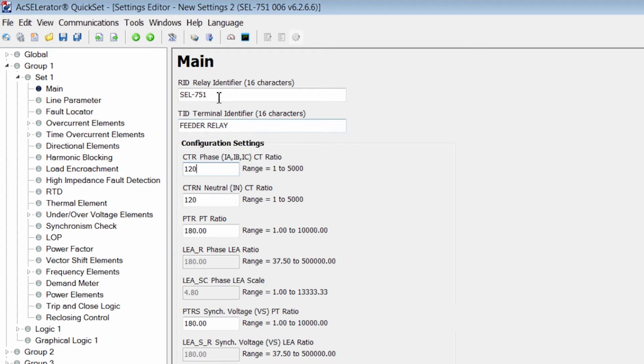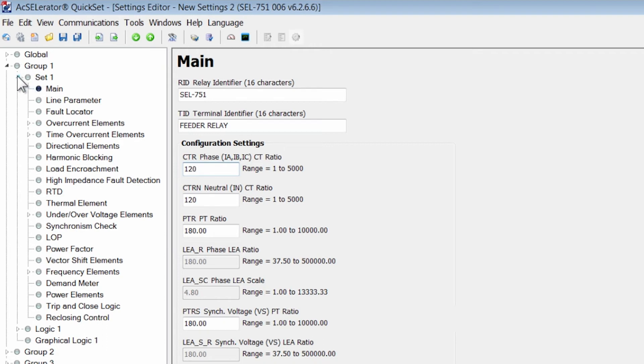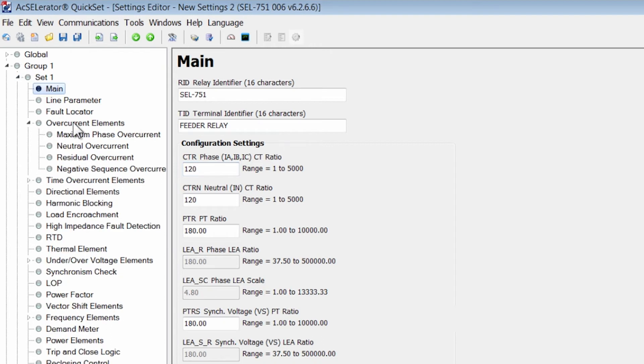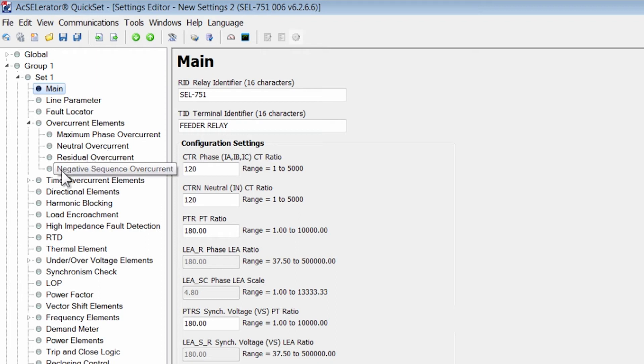Now to navigate and set the overcurrent element and the time overcurrent element, we navigate to group one, set one, and overcurrent elements. In here we have the option to program a maximum phase overcurrent, a neutral overcurrent, a residual overcurrent, and a negative sequence overcurrent element. We're going to do a maximum phase overcurrent.